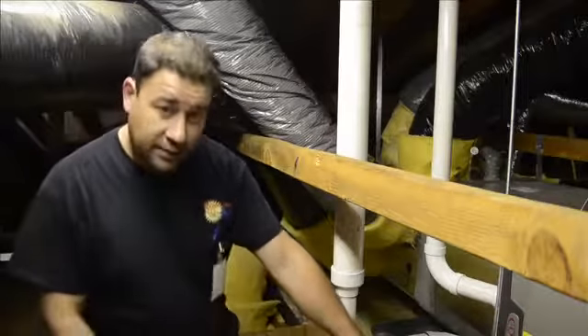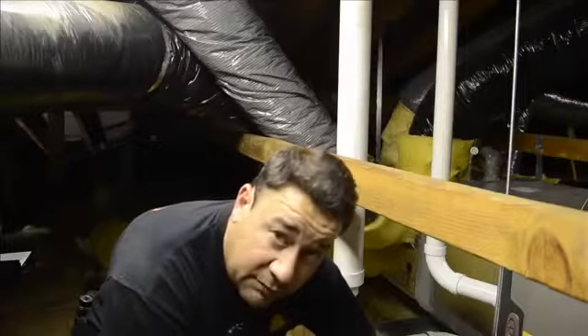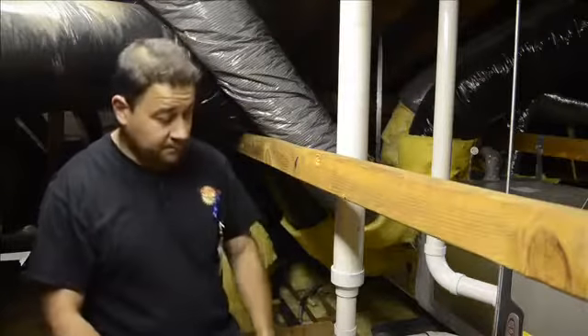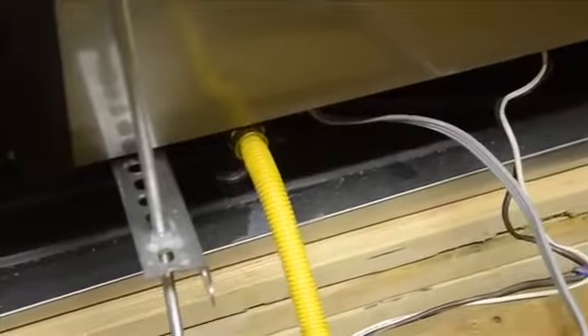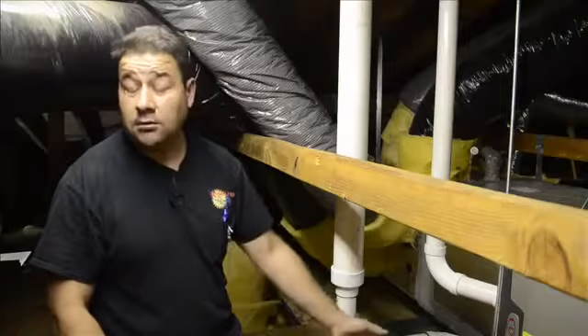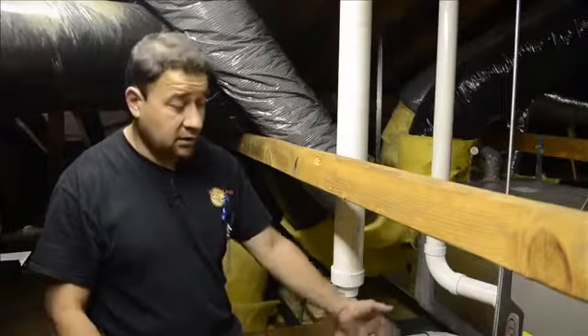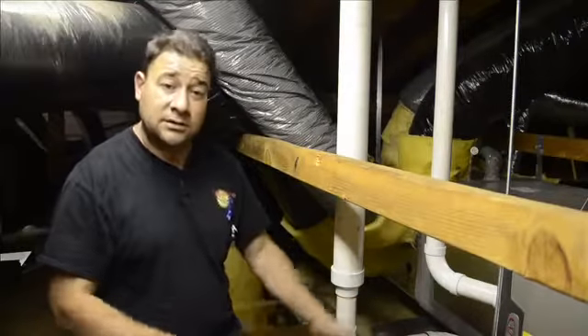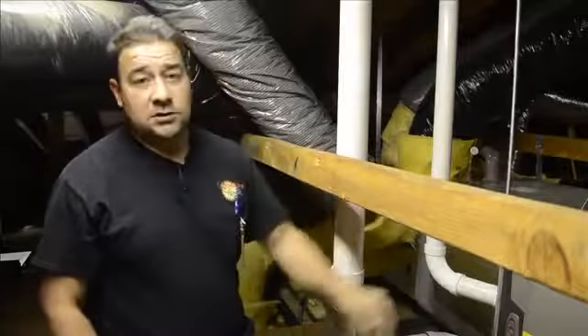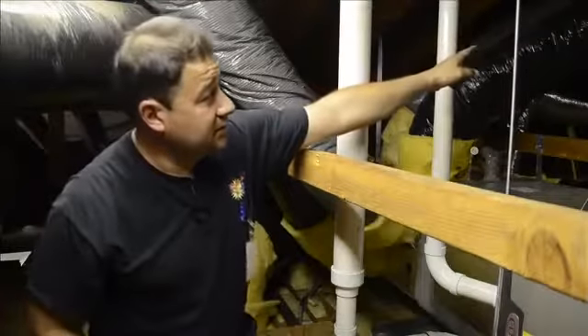Underneath here, if you want to pan over, you can see the sediment trap for the gas line. The system didn't have one before. It's to collect any sediment before it enters the gas valve. Underneath, you'll see the drain pan with 2 safety precautions in it, overflow switches. Should this drain pan ever be clogged, or the primary and secondary drain be clogged, the system won't keep running and do ceiling damage. The old system was supported by just flexible ducting straps, the old installation.